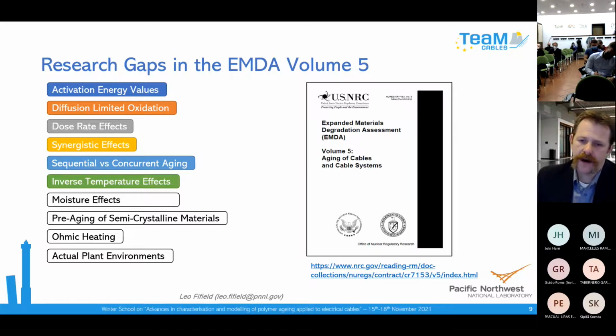For instance, before they had operating experience, they thought cables might be exposed to 50 megarads of gamma radiation over 40 years. It turns out they're exposed to much less than that, maybe 13 megarads at most in general. Temperatures assumed were also higher than actually observed. So they went back and concluded they were conservative in their estimate for 40 years, and actually it's fine - most cables can last 60 years.